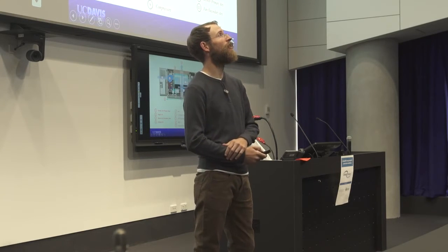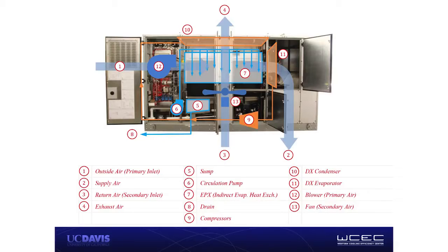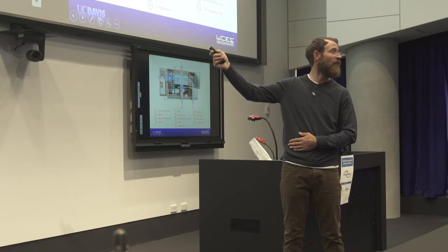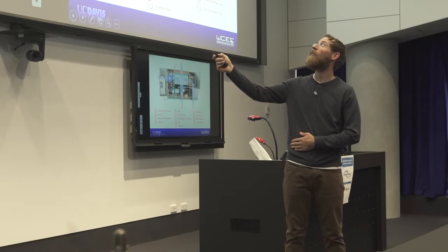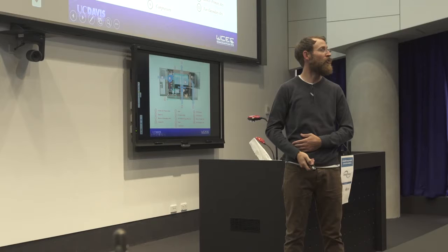This is a cross-section of how that system works. Again, it's set up as a dedicated outside air supply, so it uses no recirculation. It brings in outside air through a permanent magnet motor fan, which is very efficient, through an indirect evaporative heat exchanger core. It's cooled down. If it's not cooled far enough, then they have 2 stages of vapor compression cooling that can operate to drive the supply air temperature to an appropriate point, and then that's supplied and distributed through the building.